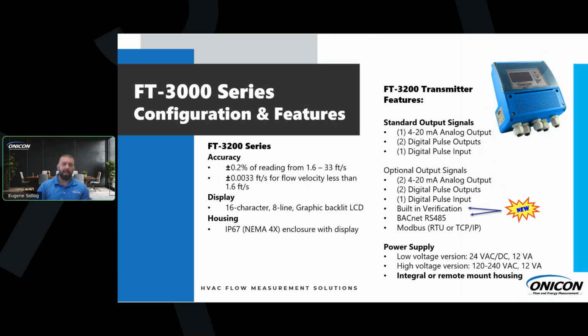Now let's take a deep dive into the two different versions of the transmitters we have for the inline mag. The FT3200 series, as we call it, is our Cadillac version of the transmitter. It is plus or minus 0.2% of reading accuracy from 1.6 to 33 feet per second. To highlight some of the features, we have optional output signals, with multiple analog output signals. We have 3 pulse inputs and outputs. We have a brand new feature called built-in verification. We have the brand new BACnet RS485, and MODBUS RS485, which is MODBUS RTU, and also TCP/IP available.